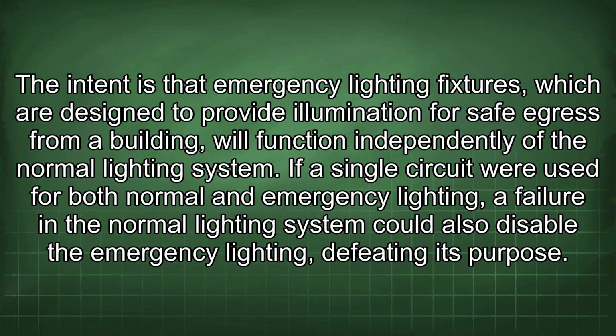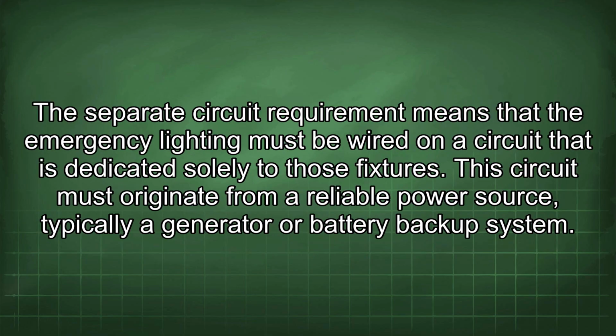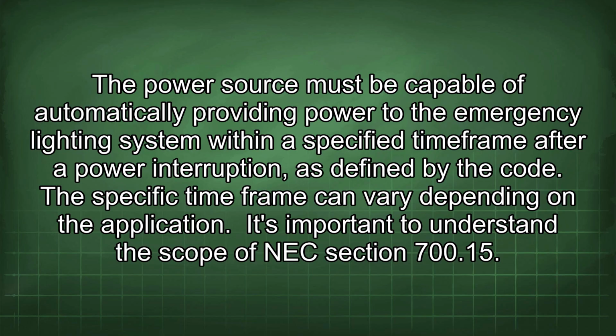If a single circuit were used for both normal and emergency lighting, a failure in the normal lighting system could also disable the emergency lighting, defeating its purpose. The separate circuit requirement means that the emergency lighting must be wired on a circuit that is dedicated solely to those fixtures. This circuit must originate from a reliable power source, typically a generator or battery backup system. The power source must be capable of automatically providing power to the emergency lighting system within a specified time frame after a power interruption as defined by the code. The specific time frame can vary depending on the application.